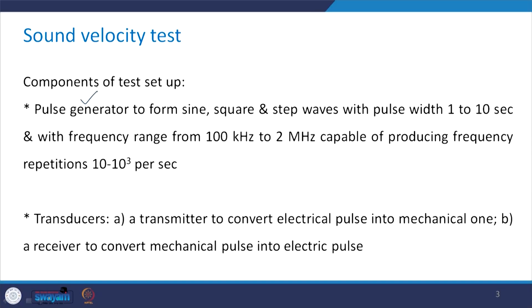The components of the test setup include a pulse generator, which can form sine, square, and step kind of waves with a pulse width of 1 to 10 seconds. It has a frequency range from 100 kilohertz to 2 megahertz and is capable of producing frequency repetitions of 10 to 10³ per second.